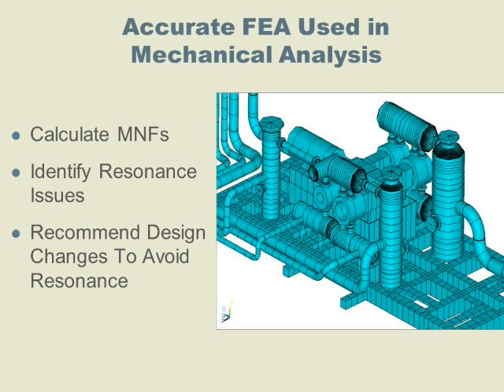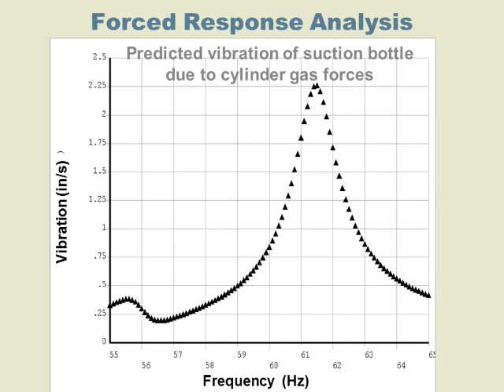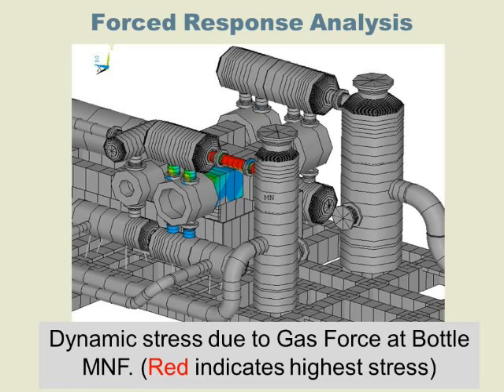The ideal solution is to modify the natural frequency of the piping system to avoid resonance. But sometimes it is impossible to do this, especially with variable speed compressors. In these cases, Beta will conduct a forced response analysis to evaluate if the predicted vibration and stress is below acceptable guidelines.